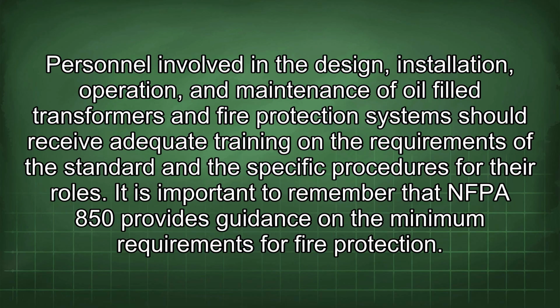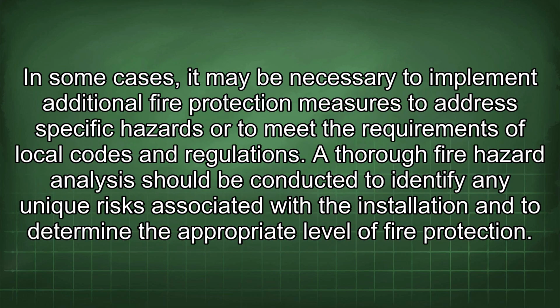It is important to remember that NFPA 850 provides guidance on the minimum requirements for fire protection. In some cases, it may be necessary to implement additional fire protection measures to address specific hazards or to meet the requirements of local codes and regulations. A thorough fire hazard analysis should be conducted to identify any unique risks associated with the installation and to determine the appropriate level of fire protection.